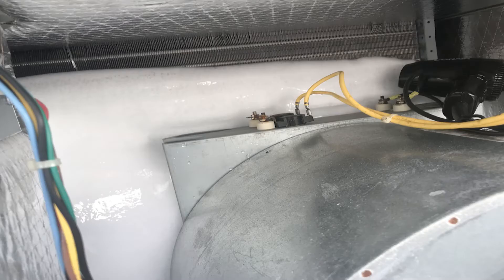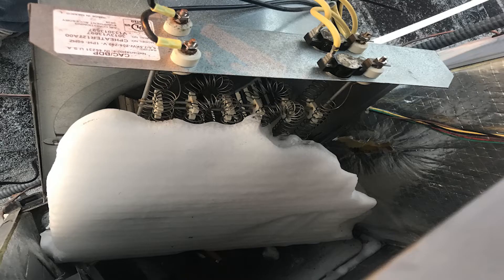As you'll see from these pictures, the coil is literally a block of ice. This was one of the coolest things when I first started training in AC that I saw. This is literally a block of ice. When they say your coil is freezing up, it is literally freezing up.